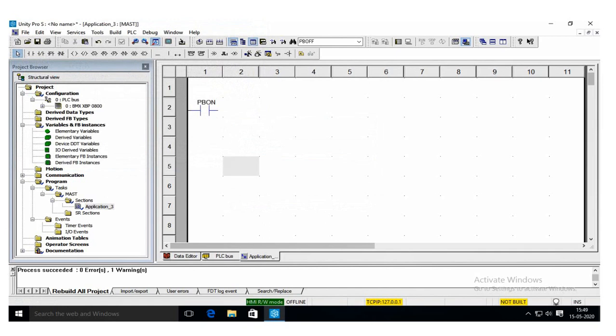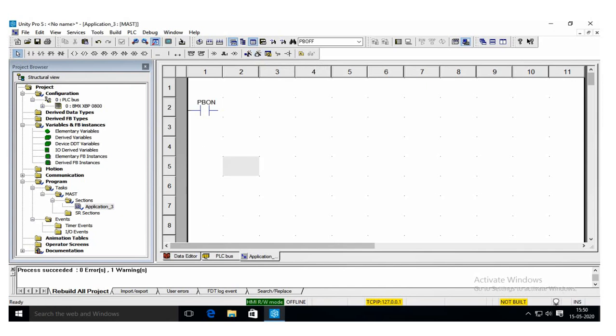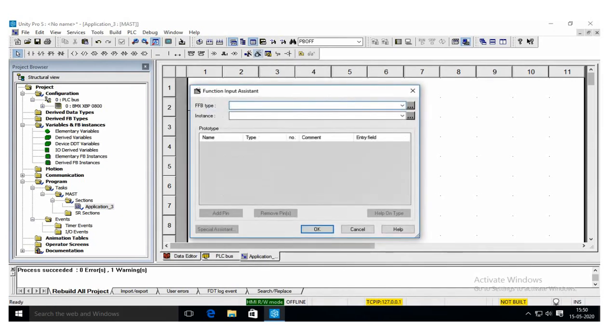A lamp LON is switched on after 10 seconds if the PBON is pressed. After 10 seconds means it is an on-delay timer, a functional block available in Unity Pro. To get that on-delay timer, go to the FFB input assistance—you can press Control+I—click that icon and type TON.